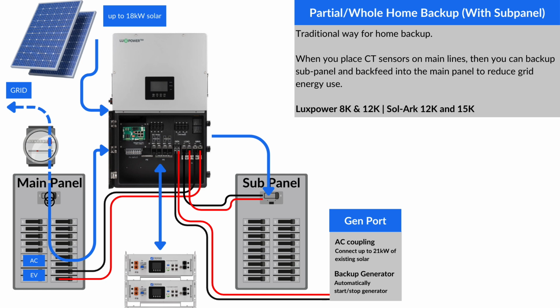A more common way of installing these inverters is with a subpanel. This gives you more flexibility in choosing which circuits you want to back up or not back up. With the included CT sensors, all of these inverters have the ability to sense how much energy is coming into the non-backed up main panel.